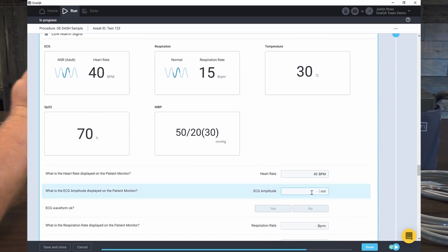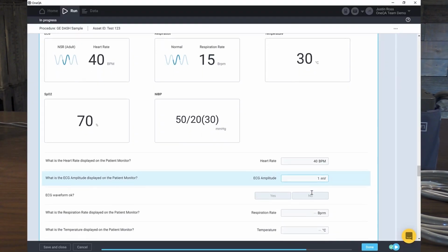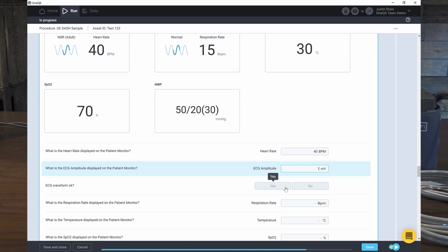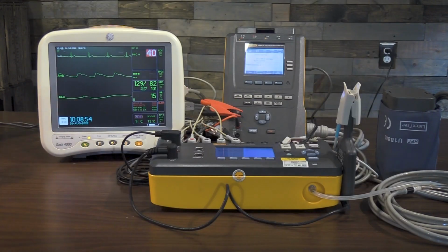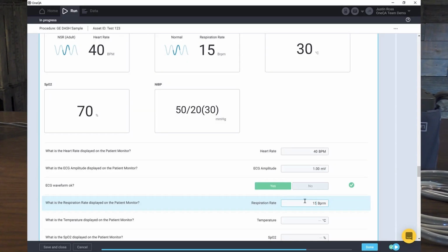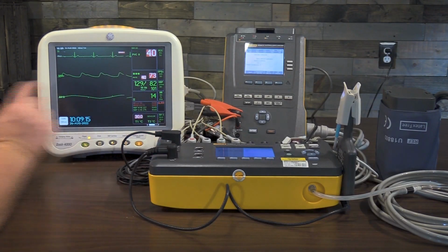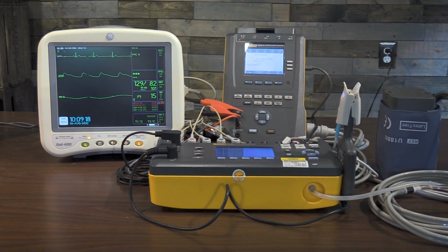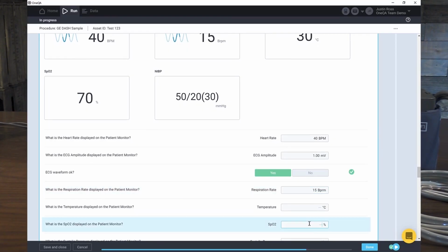The amplitude is still reading 1 millivolt. The ECG waveform still looks pretty good. My respirations are 15. I should alarm here in a little bit because our low is 5, so we're still above what our respiration rate should be. My SpO2 is at 73. The low alarm is set at 90, so let's go ahead and we'll put my SpO2 in here. 73. My temperature is reading 30. Okay.